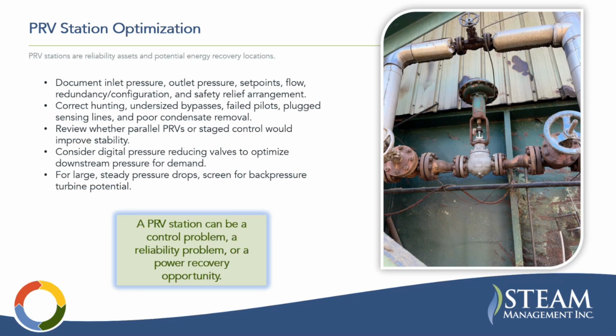PRV station optimization. For these, you want to survey these and document inlet pressures, outlet pressures, set points, flow, redundancy, configuration, and safety relief valve arrangements. You want to correct hunting, undersized bypasses, failed pilots, plug sensing lines, and poor condensate removal. You want to review whether parallel PRVs or stage control would improve stability. You want to consider digital pressure reducing valves to optimize downstream pressures for demand.